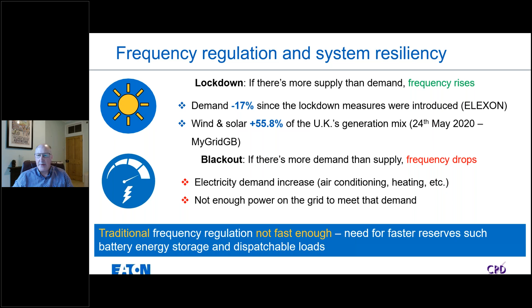To illustrate that on this slide, this is showing an example of how low frequency limits were breached. I'm sure many of you are familiar with engineering recommendations G98 and G99 that are published by the Energy Networks Association, ENA. And EREC G98 and G99 set limits for, amongst other things, grid frequency, and there are upper and lower limits. So if we have more demand than supply, our frequency goes down, and more supply than demand, our frequency goes up. We can breach the G99 set point limit for over frequency, which will trip our generator out. And likewise, we can breach the G99, G98 low frequency set points and trip our generator out. This is an example of that happening.